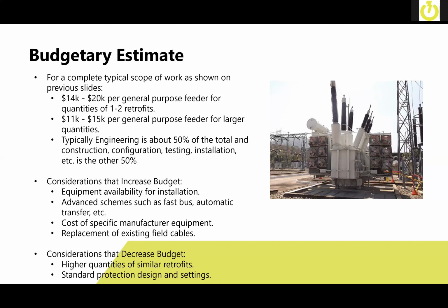Some things that may increase that budget would be equipment availability for installation. For instance, if you're trying to do multiple relays and there's only one available each day, or if there's travel required, it may increase the amount of mobilizations. Are there advanced schemes such as fast bus protection, automatic transfer, maintenance switches, etc., that need to be installed? The cost of the specific manufacturer equipment.